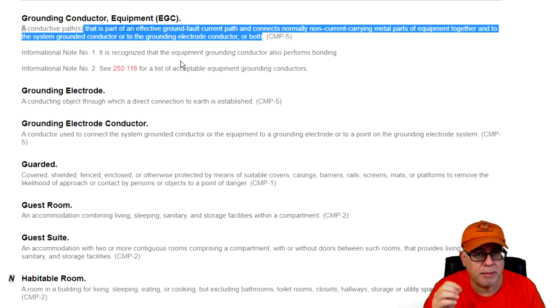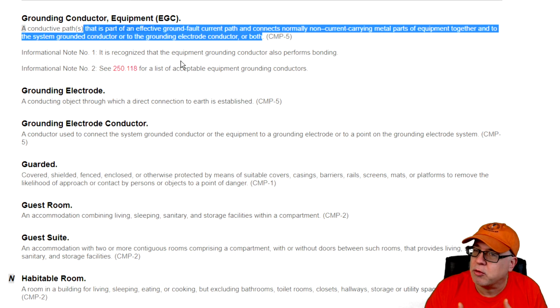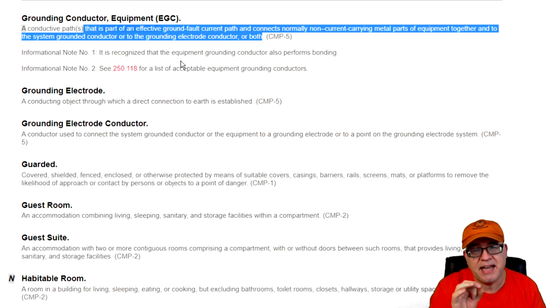It is an equipment grounding conductor that's inside of it, but they do make special MC where the armor can be used as an equipment ground, provided it has a 10 gauge or an 8 gauge, depending on the size, grounding/bonding conductor installed in it. And you just cut that off at the end. You don't terminate that. That's just to make connection to all the convolutions. So you've got all that.